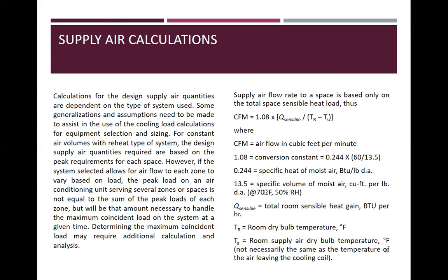However, if the system selected allows for airflow to its zones to vary based on load, the peak load on an air conditioning unit serving several zones or spaces is not equal to the sum of peak load of each zone, but will be that amount necessary to handle the maximum coincident load on the system at a given time. Determining the maximum coincident load may require additional calculation and analysis. So supply airflow rate to a space is based only on the total space sensible heat load.